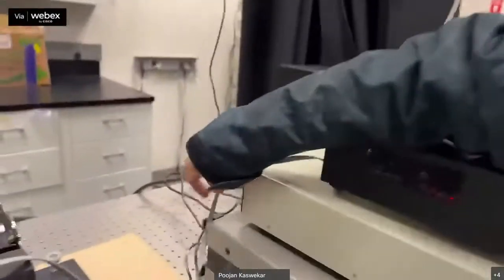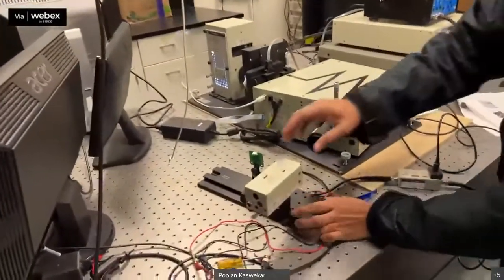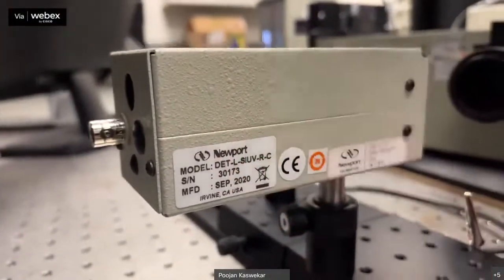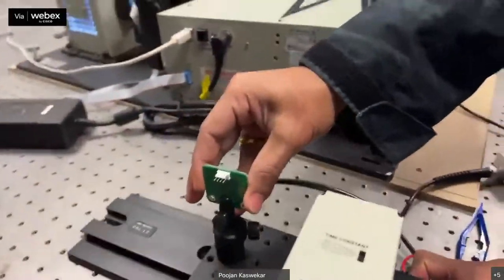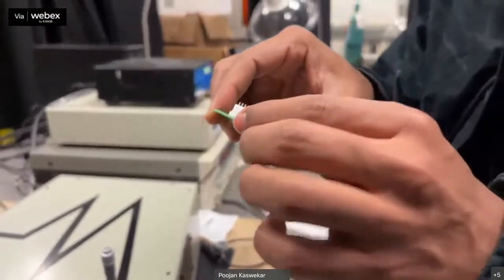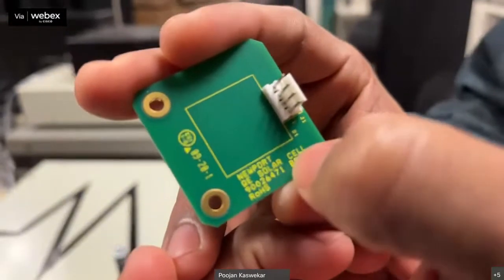And this is for adjusting the chopper. For chopper adjustment, you connect this one. See here, this cable will communicate this one to the chopper. And this instrument will control how much voltage you are applying to the measuring instrument. These are two of my measuring instruments. This is called the detector, DET-L-SIUV. This is my detector, and this is my solar cell for the measurement support, supplied by Newport. This one is calibrated and supplied by Newport for the QE solar cell.